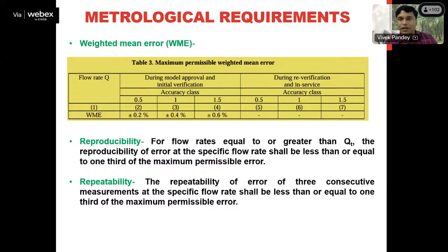So you can see that for re-verification and inspection there is no value specified for weighted mean error because it is not required. And in model approval and initial verification, for accuracy class 0.5, weighted mean error should be plus minus 0.2%. For accuracy class 1, it is plus minus 0.4%. For accuracy class 1.5, it is plus minus 0.6%. Now, later on, I'll be speaking about the test which is performed on the gas meter during model approval and initial verification as well as re-verifications. I'll be discussing these two parameters, reproducibility and repeatability.